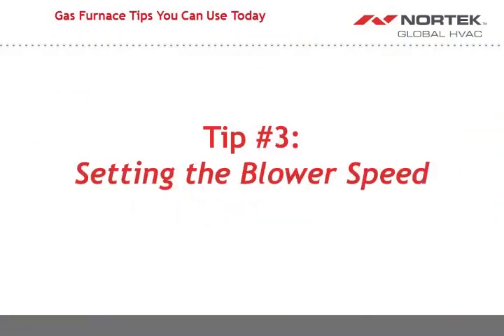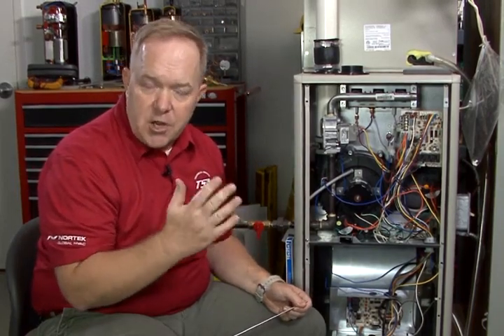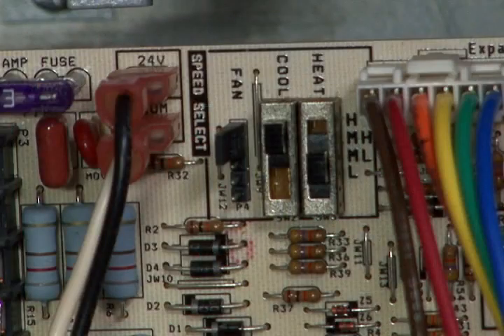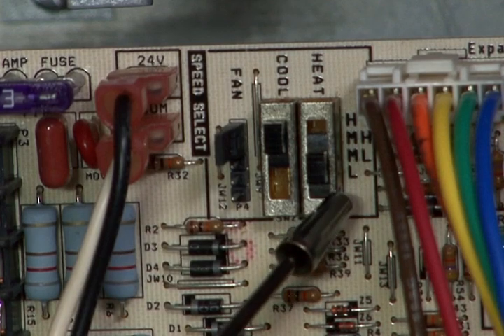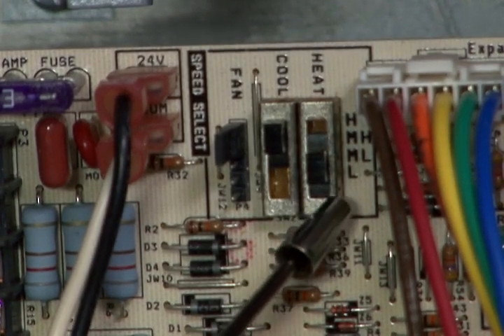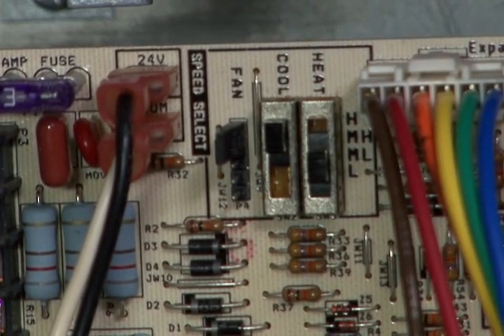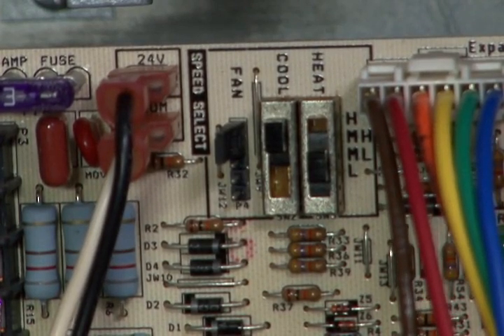Tip number 3 is concerning setting the blower speed on single-stage gas furnaces, and that's very, very simple to do. You basically have 3 options, if you will, when it comes to the single-stage gas furnaces. If you look at the very top of the ignition control board, you're going to have one switch labeled heat, one switch labeled cool, and then off to the side here, you have a black plastic jumper shunt. If you look off to the side of where the switches are located, you'll see H, MH, ML, and L. That's high, medium high, medium low, and low.